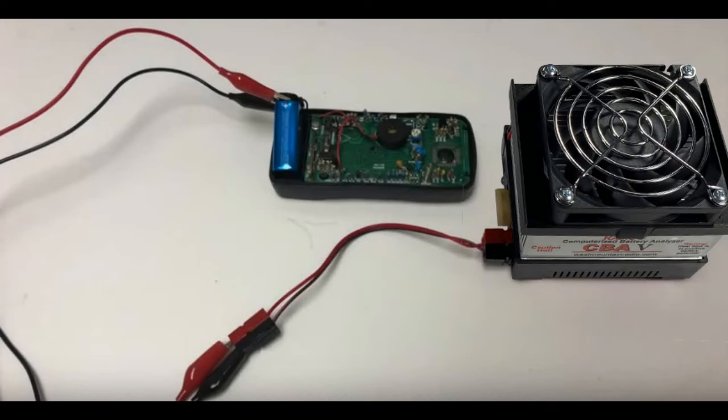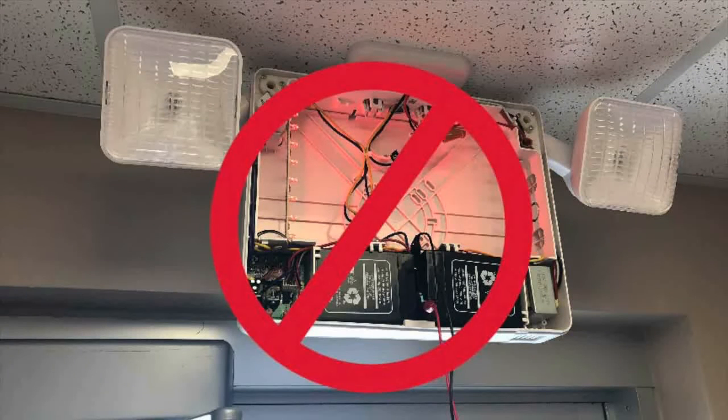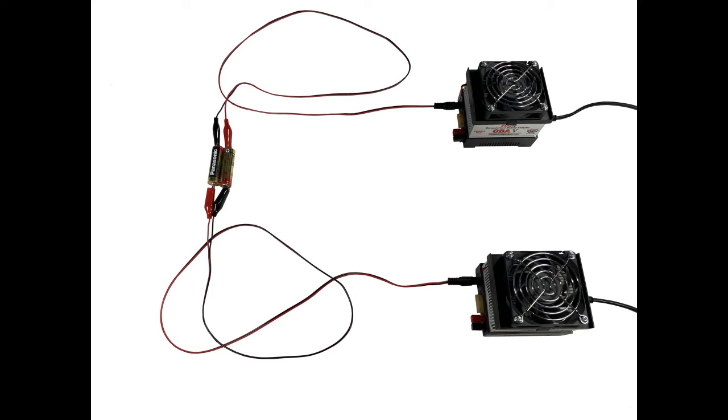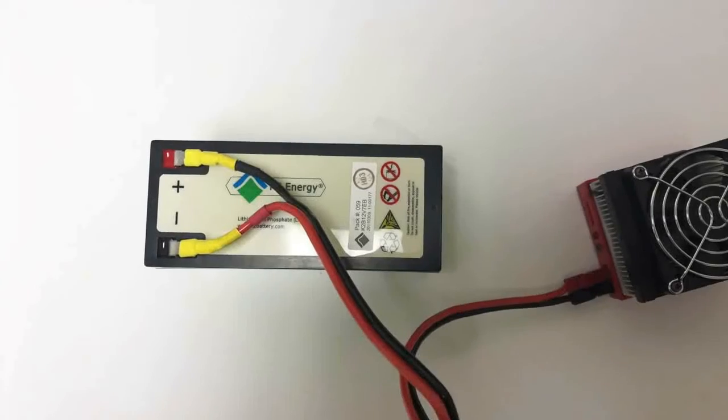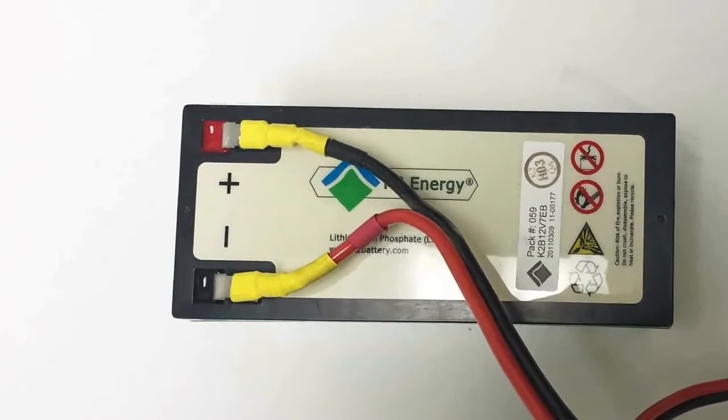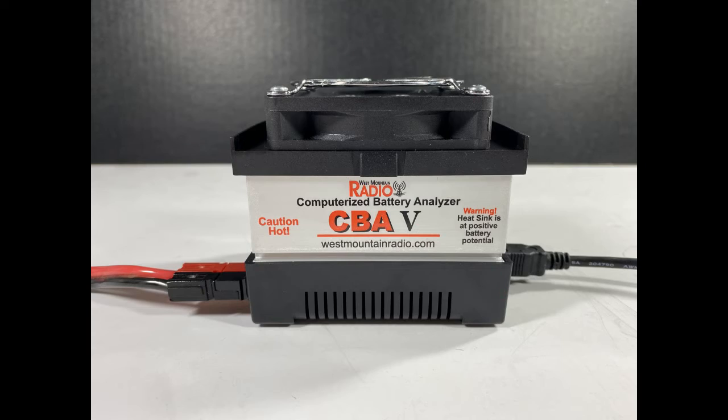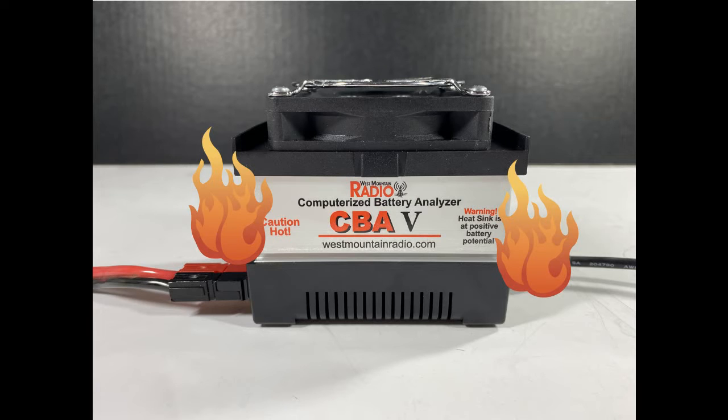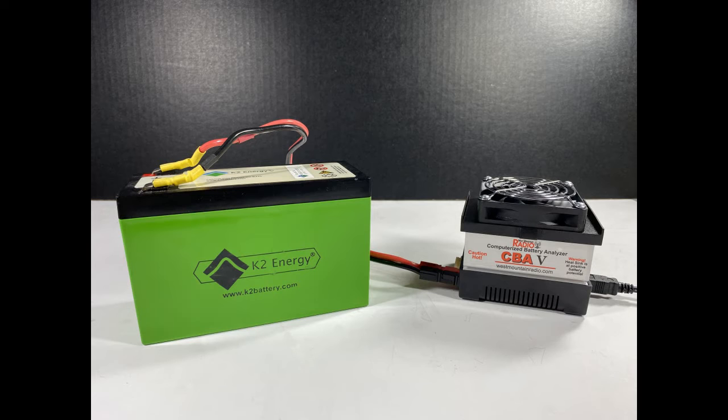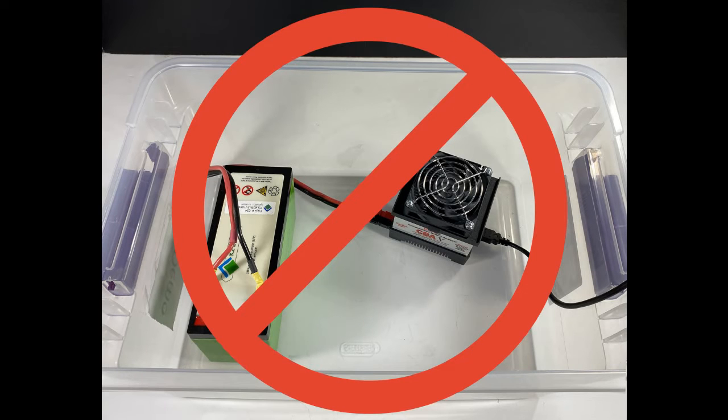Do not have the battery connected in a circuit or anything else that has a path to ground. If multiple CBAs are connected to the same PC, make sure that none of the batteries being tested are connected together. Never reverse the polarity. The heat sink on the CBA 5 can get hot and is not at ground potential. Be careful. If you are testing a 48-volt battery, the heat sink will be 48 volts. While running, the CBA should not be in an airtight closet or enclosed container. The heat sink needs access to open air for proper cooling.